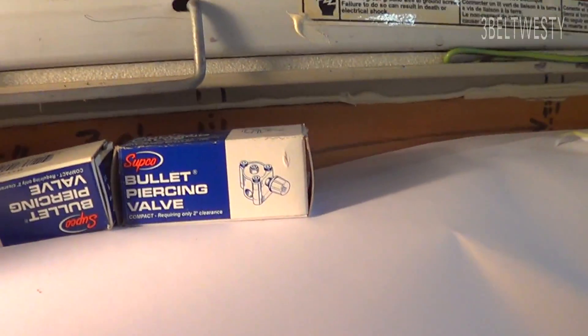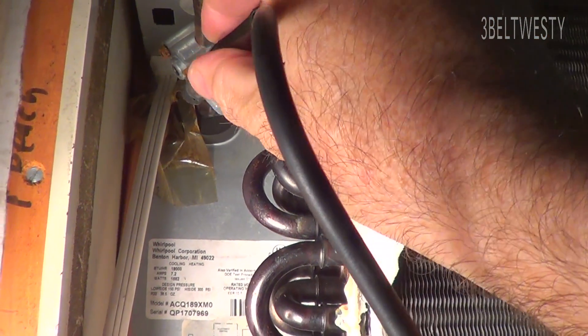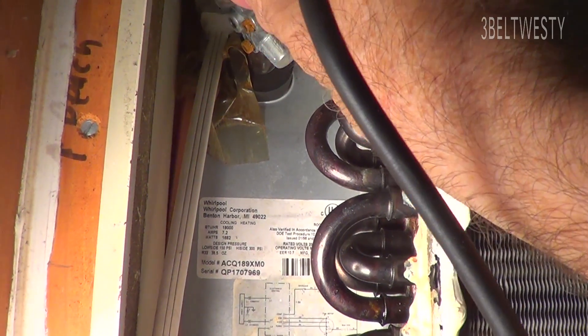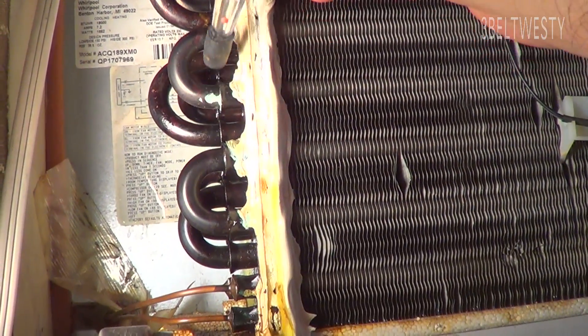There it is, red hot. And I'm going to take the probe. Got a piercing bullet valve over here — temporary. I've got just a little bit of nitrogen and freon in there. There's the leak... right there. I found the leak to be right along in here.